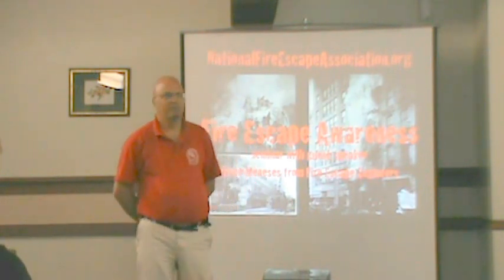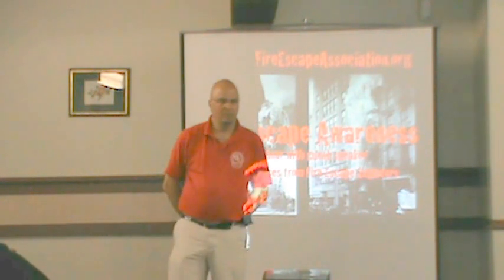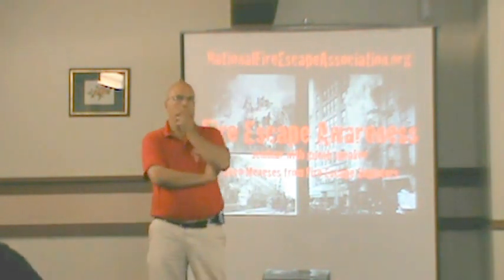So those, a lot of times we'll get calls, or not a lot recently, but in the past, through the years, I have run into this. Those hydraulic ladders leak because the seals are not properly redone as often as they should be. They leak, and then with the accumulation of the oil, it turns into grease. We'll write them up because obviously it's a slip and fall type of thing. If somebody were to grab onto that, they're just going to fly off of it. So we'll go in and scrape it all off.